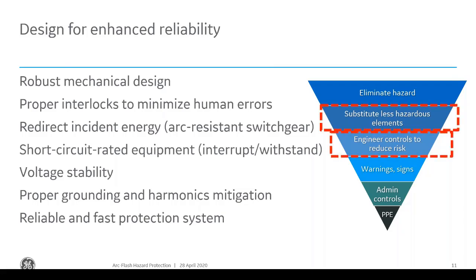But looking at this upside-down triangle, as I mentioned, we really cannot eliminate the hazards. The best we can do is provide some sort of engineering controls to reduce the risk, or substitute less hazardous elements. The other techniques are proper PPE, proper interlocking, admin controls, and warning signs to tell personnel working in front of an arc flash zone to take the proper mitigation techniques, such as wearing PPE or even staying away from the arc flash zone.